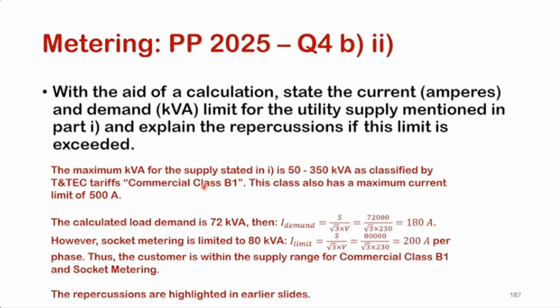Nice. So here now, you see, with the aid of a calculation, state the current in amperes and the demand kVA limit for the utility supply mentioned in part 1 and explain the repercussion if the limit is exceeded. So the maximum kVA for the supply stated in part 1 is 50 to 350 kVA. Right? And this is classified as commercial class B1 in the tariff. And this class also has a maximum current limit of 500 amps. They give us the load demand of 72 kVA. So if we calculate the load demand from the customer, it should be S, they are found out 72 kVA, divided by root 3 times the voltage. So 72,000 over root 3 times 230, you get 180 amps.